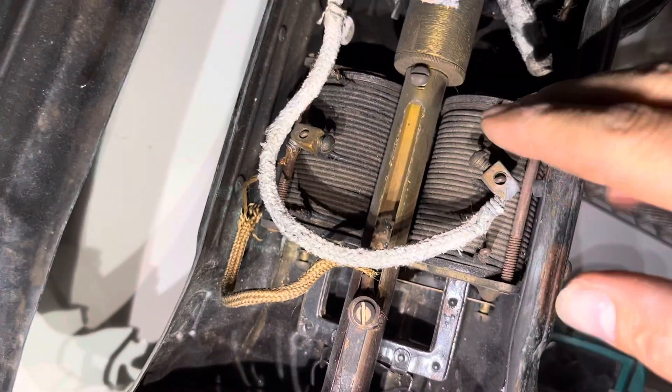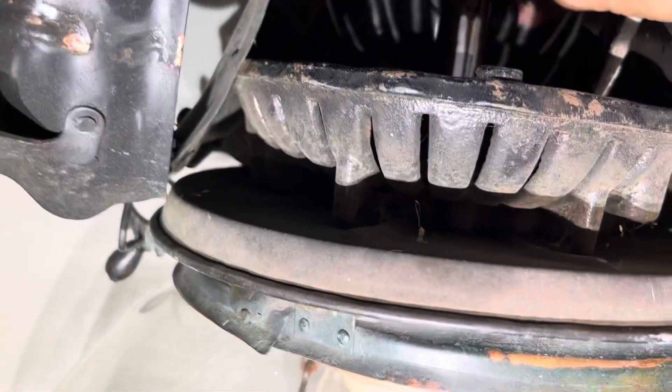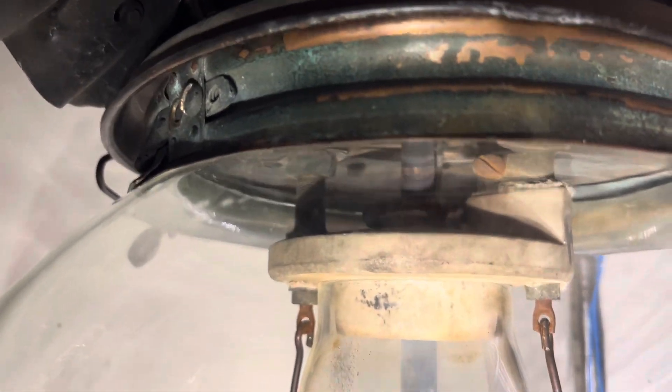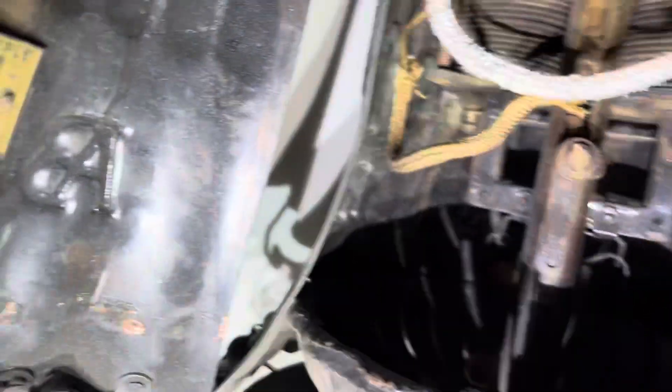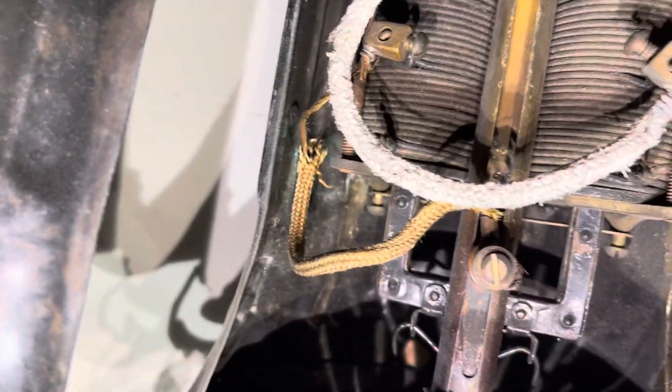So when you turn this on, this coil gets sucked up. And what that does is there is a clutch mechanism made of a porcelain disc which lifts the rod. When you turn it on, that lifting coil comes up and it pulls the upper carbon up, striking the arc and adjusting it to the appropriate gap.